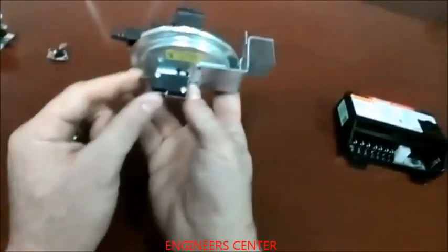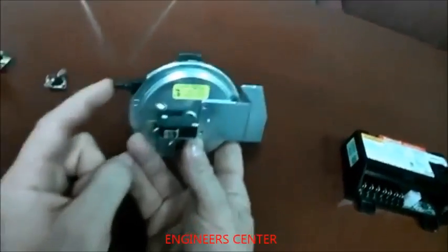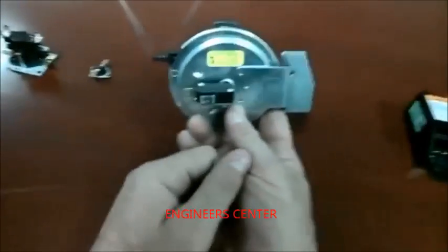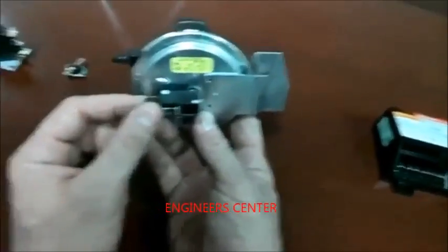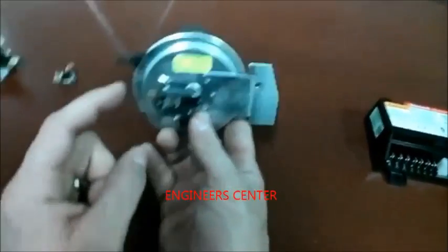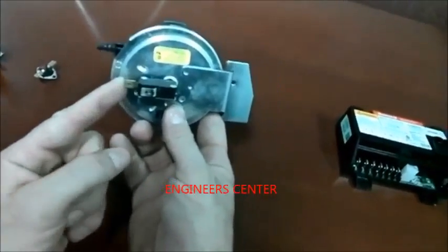Here, we have another. This is a pressure switch, but it's just a relay, guys. It just opens and closes, but this one opens and closes according to pressure. So just like the rest of them, it'll open and close. You know how to test all these things, because all they do is open and close. You get a meter, you put it on continuity, see if they open and close, or you just put your meter on voltage, and if you have voltage here, and it doesn't have voltage here, then you know it's open.